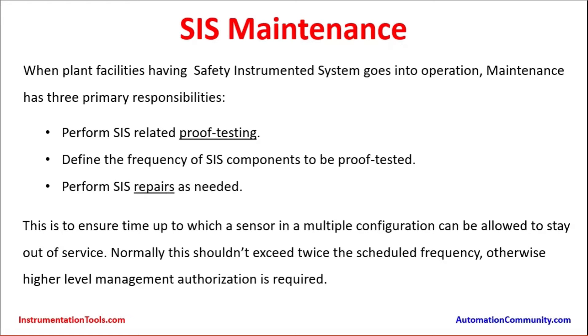Normally this should not exceed twice the scheduled frequency; otherwise, higher level management authorization is required. For example, if the sensor is calculated to be proof tested every three years, then the maximum it can extend is up to six years. If proof testing cannot be done without exceeding the due date, it calls for a SIS repair deferral and must go for higher level management authorization.